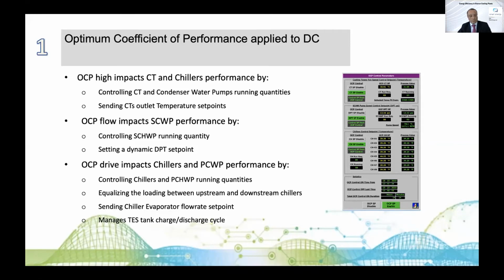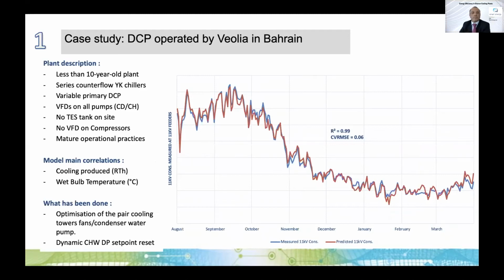The second module that is incorporated in this solution is an optimizer of the distribution system, the chilled water distribution system. We've developed a novel way to distribute chilled water on large districts by finding the hydraulic minimum for the distribution to ensure that all the customers are just supplied. And finally, the module we call OCP Drive is a plant sequencer. It controls the plant as would the ideal plant operator, never making any mistake and always finding the right combination of equipment to minimize the plant consumption while ensuring quality of supply to all the customers. So this is the tool, and we're going to go through 2 case studies.